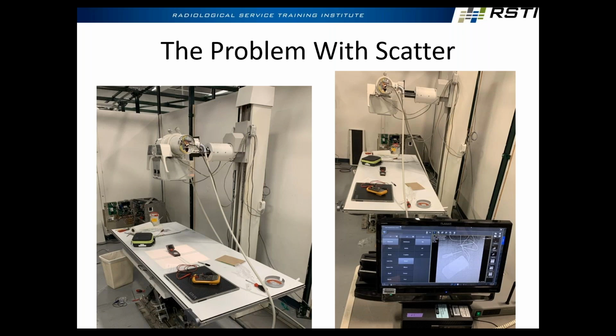What I did here, look at this picture. This is an over table x-ray room. You can't see it from where you're sitting, but here's the collimator. See the light right there? I'm collimated down to this detector on this little sensor. I put a detector next to the detector. It's not in the beam at all. This detector is what's called an AED, automatic exposure. I forget what the acronym stands for, but it's an aftermarket detector that basically will trigger when it sees radiation. So it doesn't require any interface with the generator. You can just plug it in. When it sees radiation, it starts to trigger, and it stops recording once it sees the radiation stopped.